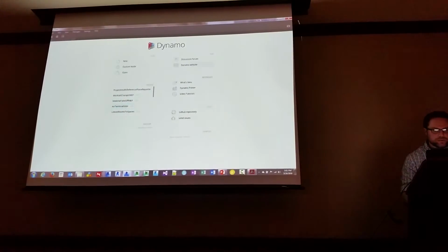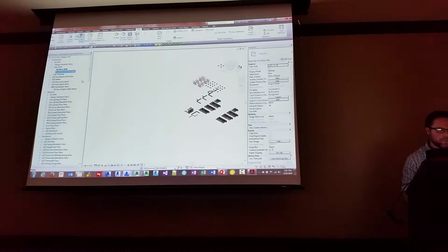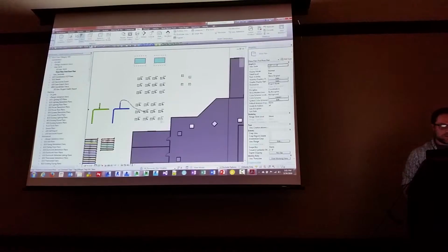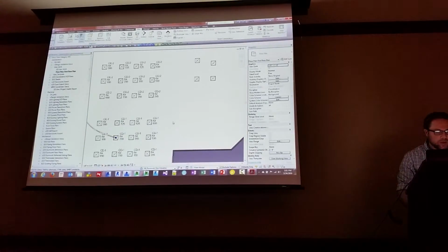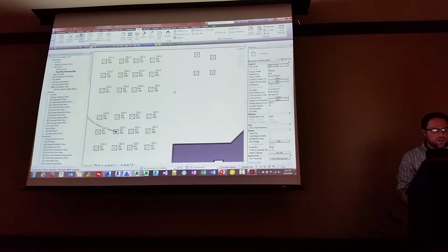Okay. So for starters, let's go to a floor plan view. And just kind of ignore all the weird stuff going on. This is my sandbox model. Is everybody able to read the tags? Because that's going to be kind of key here. You guys all see that? Okay. All right. As you can see here, I have all of these air terminals with different flow values, but they're all 6-inch. Okay, that would never happen.